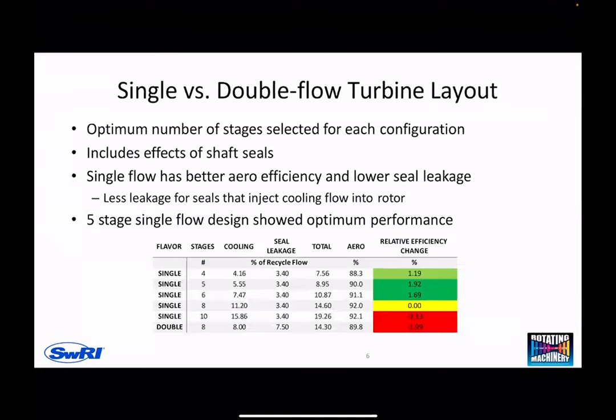So what we wanted to do is take all of the flows going into the turbine between the single versus double flow configurations, and see what the relative efficiency change is - not just in terms of turbine performance, but actually in terms of cycle performance. So what you see is the table on the bottom, which is what we used to determine our optimal turbine size.